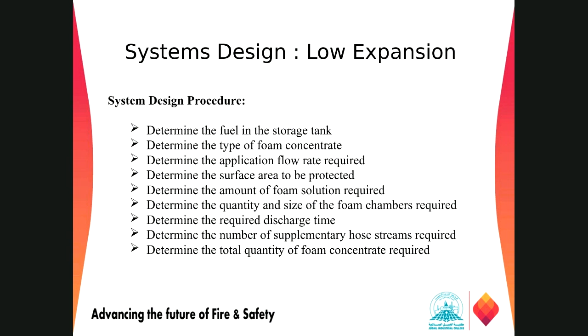Based on the surface area, we can calculate the foam solution required and the quantity and size of the foam chambers, in this case based on the diameter. Then the time duration for the application, maybe 10 minutes, 20 minutes, 30 minutes, all the way up to 60 minutes for different requirements. And the supplement hose stream required, based on the diameter of the tanks again, along with a 50 GPM increment for more allowances. And at the last, determine the total quantity of foam concentrate required for these applications. These are some of the steps for the foam system design application.